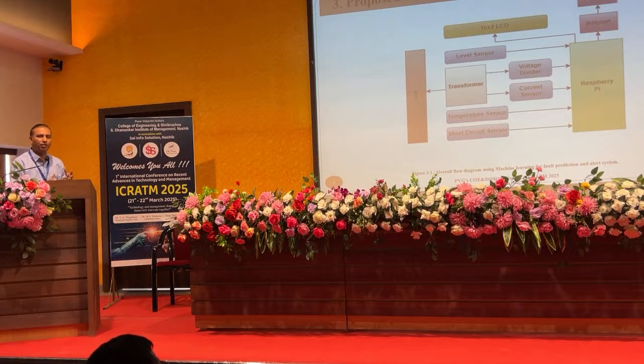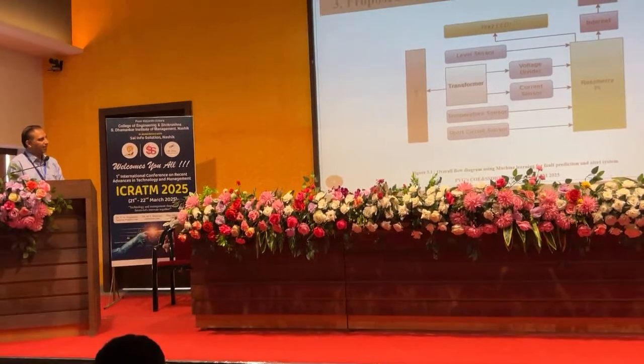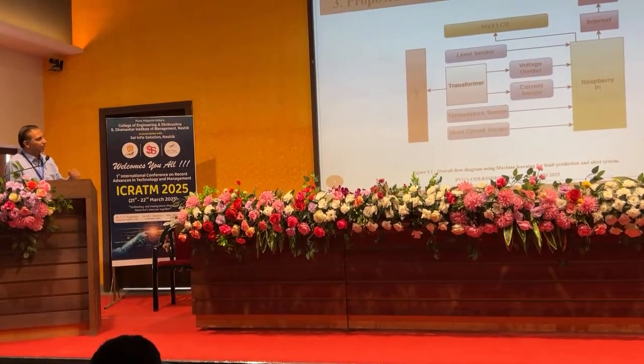As per the transformer's weightage, wattage, and its ability to supply power, the efficiency or take-up time of the sensors can be changed. In the proposed model we are using four sensors, which will be real-time monitoring the transformer and giving this information to the Raspberry Pi. From the Raspberry Pi, this information goes to the internet and is given to the monitoring station, where it is continuously monitored, and if the threshold parameter is touched, automatic sensing and fault detection is done.